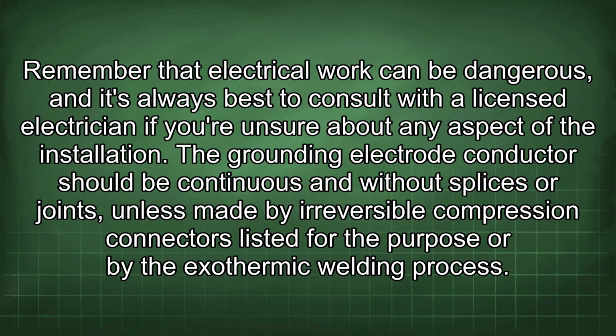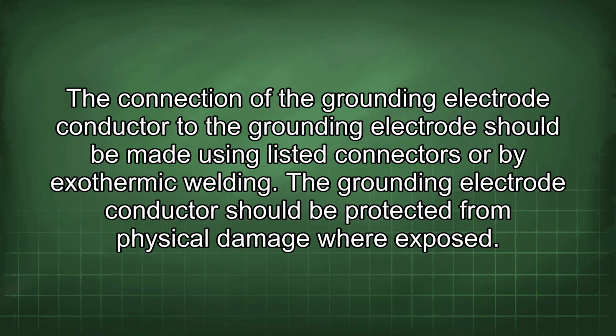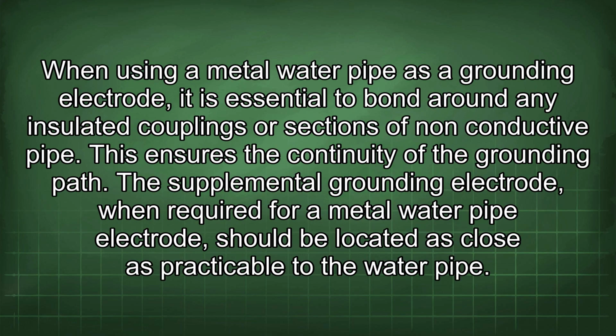The grounding electrode conductor should be continuous and without splices or joints, unless made by irreversible compression connectors listed for the purpose or by the exothermic welding process. The connection of the grounding electrode conductor to the grounding electrode should be made using listed connectors or by exothermic welding. The grounding electrode conductor should be protected from physical damage where exposed. When using a metal water pipe as a grounding electrode, it is essential to bond around any insulated couplings or sections of non-conductive pipe. This ensures the continuity of the grounding path.